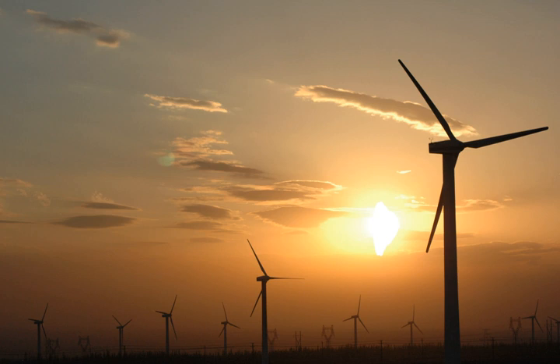Another problem is that wind companies find out after the fact that the transmission capacity of a new farm is below the generation capacity, largely because federal utility rules to encourage renewable energy installation allow feeder lines to meet only minimum standards. These are important issues that need to be solved, as when the transmission capacity does not meet the generation capacity, wind farms are forced to produce below their full potential or stop running altogether, in a process known as curtailment. While this leads to potential renewable generation left untapped, it prevents possible grid overload or risk to reliable service.